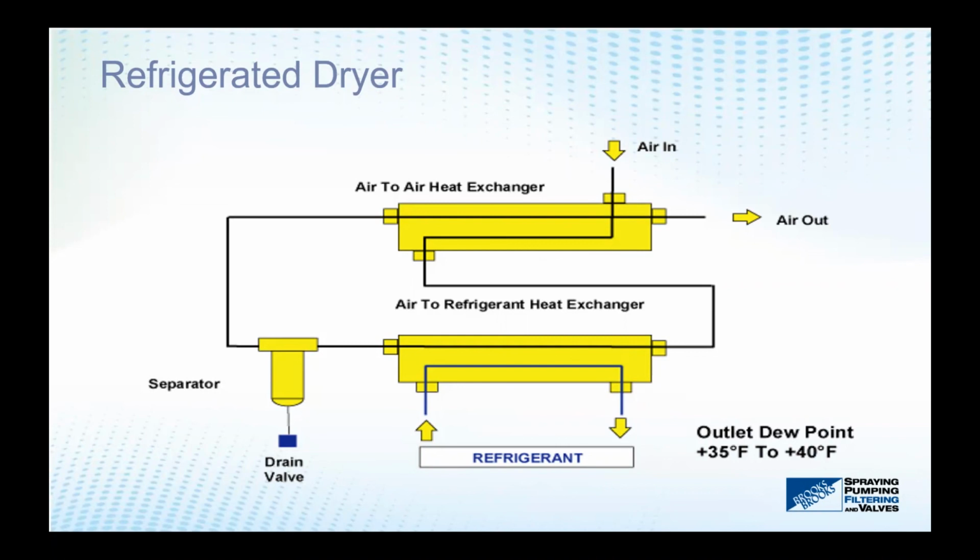Good point, Russ. For the Canadian climate, we would never want to use these if your airlines are going outdoors. Because I don't think there's anywhere in Canada where the temperature doesn't go below freezing point. So this would be a definitely negative design for outdoor line applications.